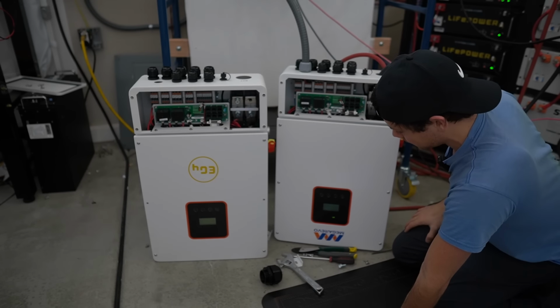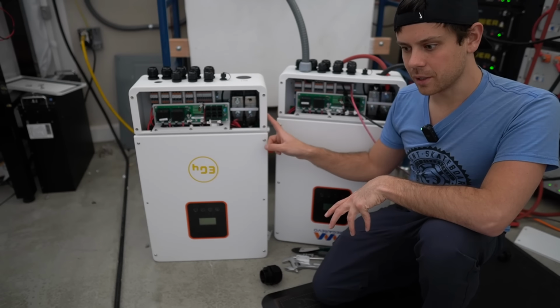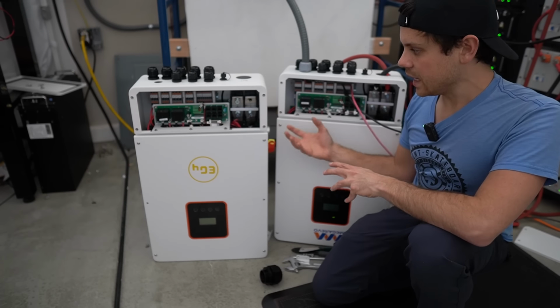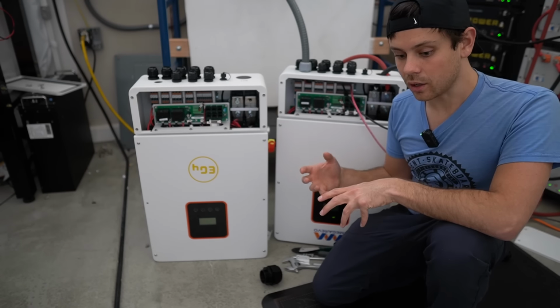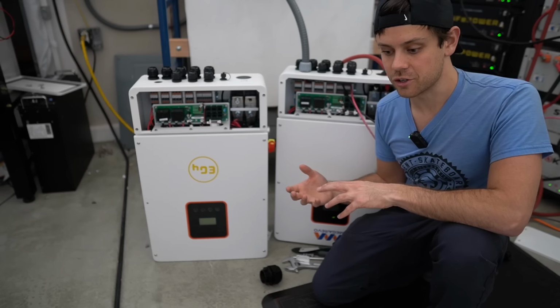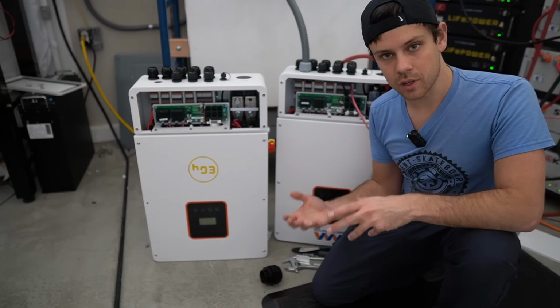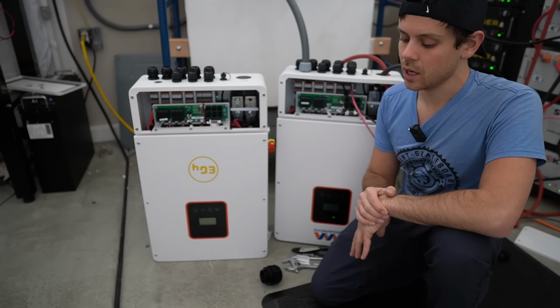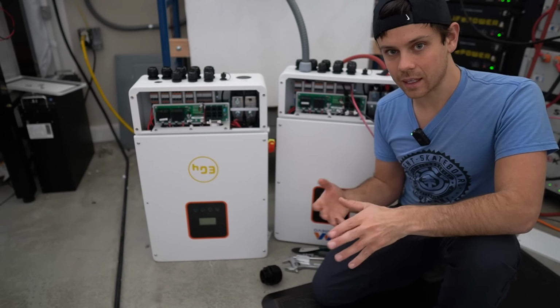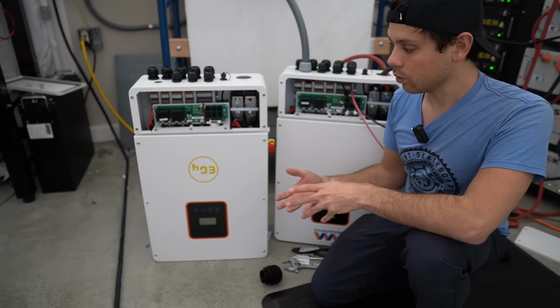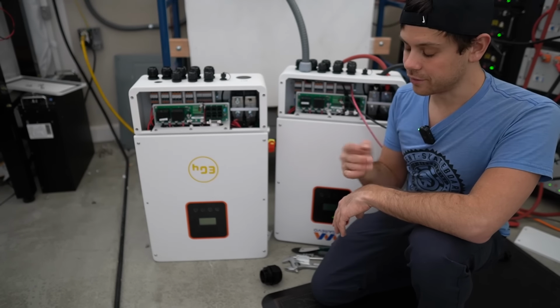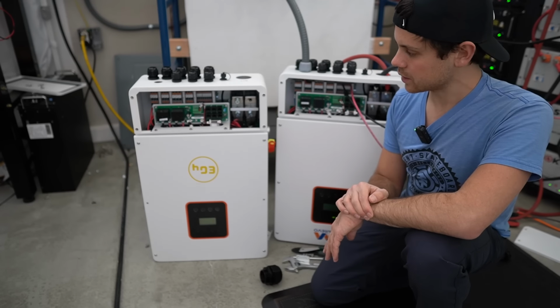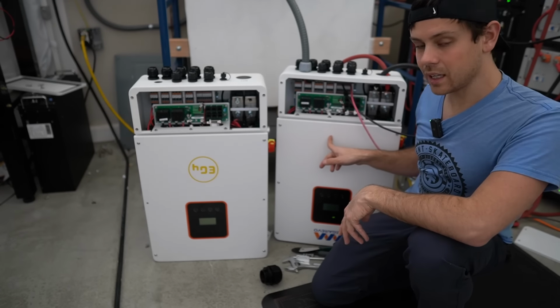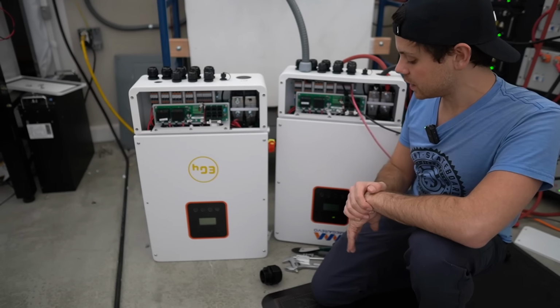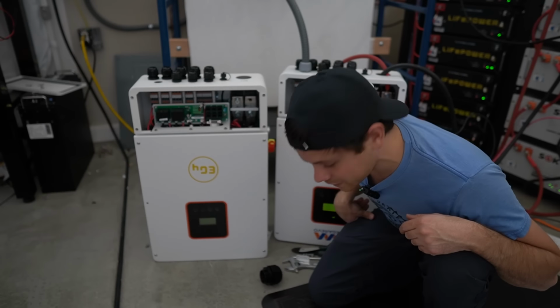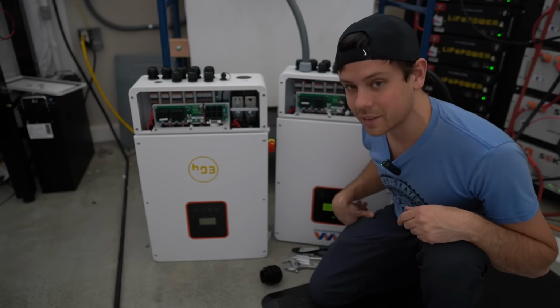This one works flawlessly. Another feature I forgot to mention on these inverters is that each hot leg by itself can handle 4,500 watts. So your loads do not have to be necessarily balanced, but you cannot exceed 8 kilovolt amps total. But one leg can handle 4,500 watts, which is pretty interesting. And right now we're actually exceeding the max output and it's still running it just fine. And the leakage current is 13 milliamps, so that's not the issue at all.